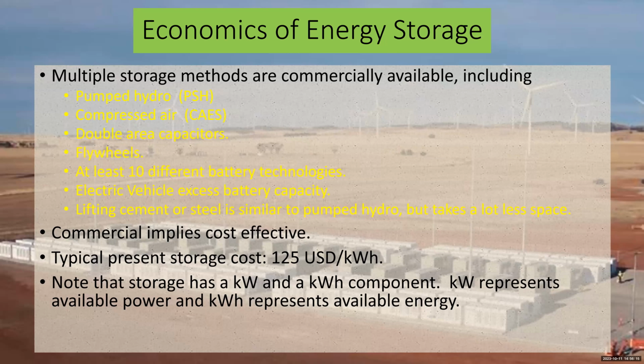Storage has kilowatts and kilowatt hours, because kilowatts are what you're using on an instantaneous basis. Every storage source has a limit to the number of kilowatts that can be developed at any instant in the discharge cycle. If it's lithium, and you have a 10 kilowatt hour storage, your kilowatts is typically going to be more like 4 kilowatts available, and then it's current limited. So you just need to know that you're storing energy in kilowatt hours, but you're taking it out in terms of kilowatts. That is the rate at which you remove it from storage, and that's how people use it, is the kilowatts.